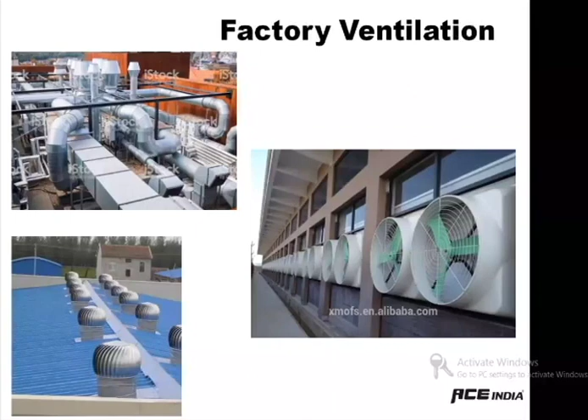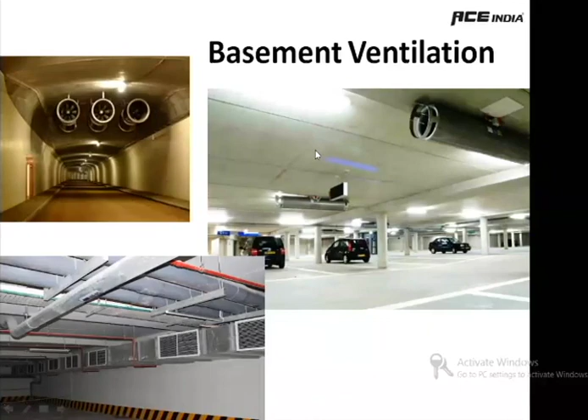Here generally you have car parks when you have minus floor levels, -1, -2, or -3. Generally car parking means there will be a buildup of carbon dioxide, carbon monoxide, or other flue gases or exhaust gases inside the basement, because you don't have any sort of natural ventilation happening there. So you have to force the issue by using fans, maybe ducts, axial fans. The one you are seeing here is called a tube axial fan. Understood? So these are the ways you can see as a basement ventilation system.